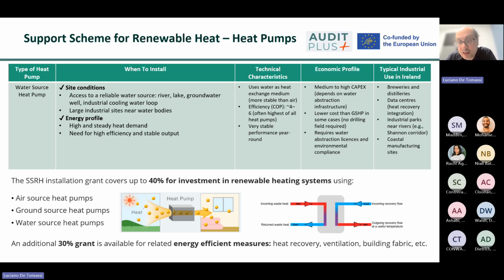In summary, air source heat pumps offer the greatest flexibility and lowest barriers to deployment, but with more variable efficiency. Ground source heat pumps provide the most stable and efficient long-term performance where site conditions allow, and water source heat pumps offer high efficiency but are constrained by water access and regulatory complexity. Under the renewable heat support scheme, the optimal choice should be based on a combined assessment of heat demand characteristics, required temperature levels, site constraints, grid capacity, alongside the opportunity to enhance system performance through complementary energy efficiency measures supported by this scheme.